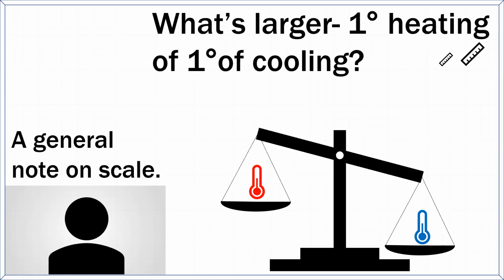But when you're talking about building science, when you're talking about HVAC, you're not talking about pure temperatures or pure degrees - you're talking about temperature differences. If 95 degrees is a hot day, or 100, or 105 - let's do easy math and say it's 95 - if you're trying to shoot for 75 degrees in the house, that gives you a 20 degree temperature difference. So every degree of that is 5%. You change the temperature by 3 degrees, you're having a 15% impact on the temperature differential, which is what actually matters in load calculations.